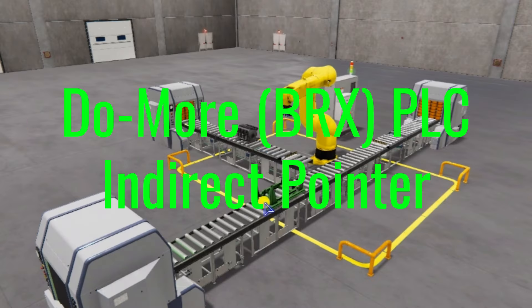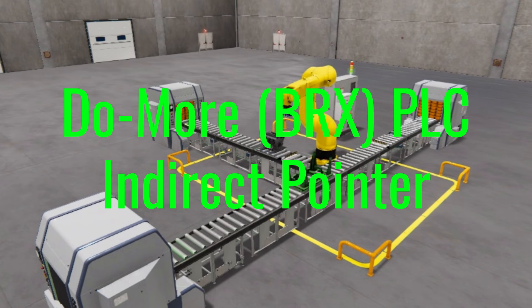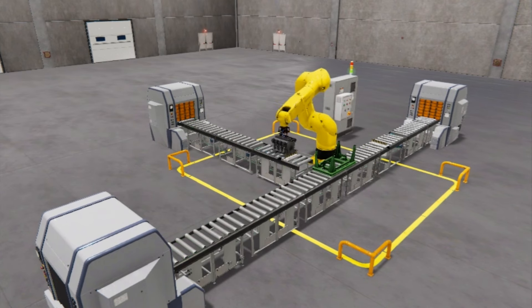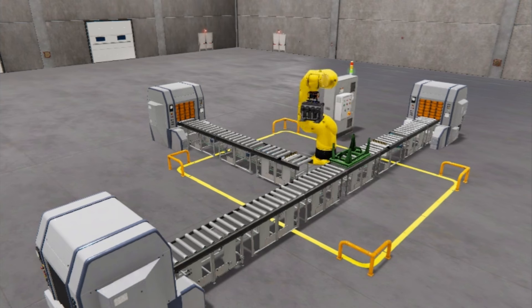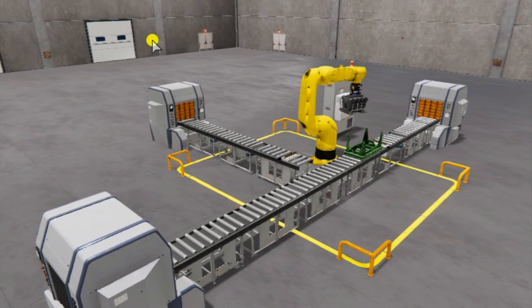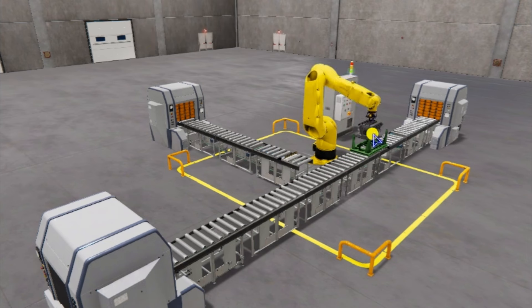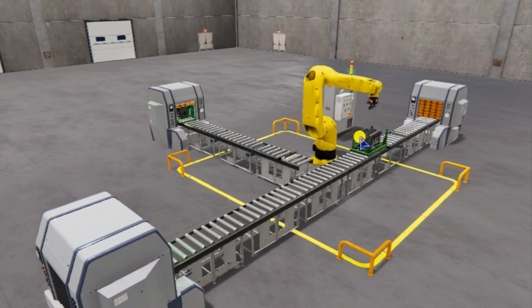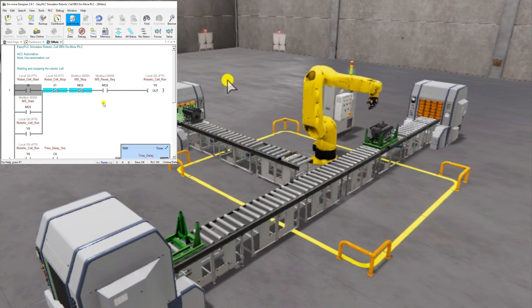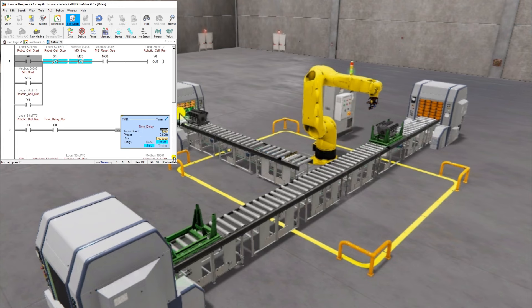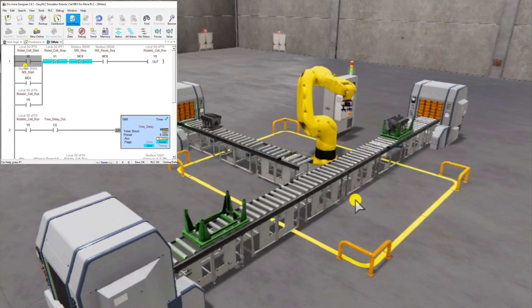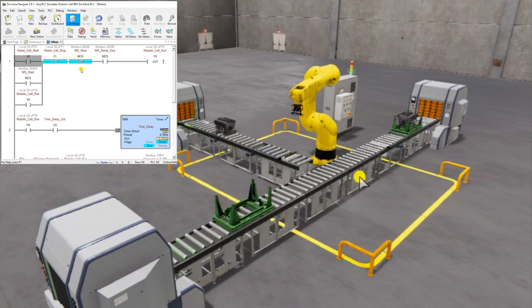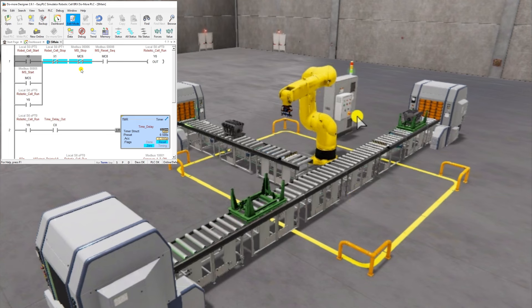Do More (BRX) PLC Indirect Pointer. Indirect addressing allows an instruction's memory address to be varied when running to point to multiple locations. All of the data blocks in the CPU can be used as arrays. This includes the ones that you can define yourself. The array index must be in the range of 0 to 65535 and must be stored in the V memory location.